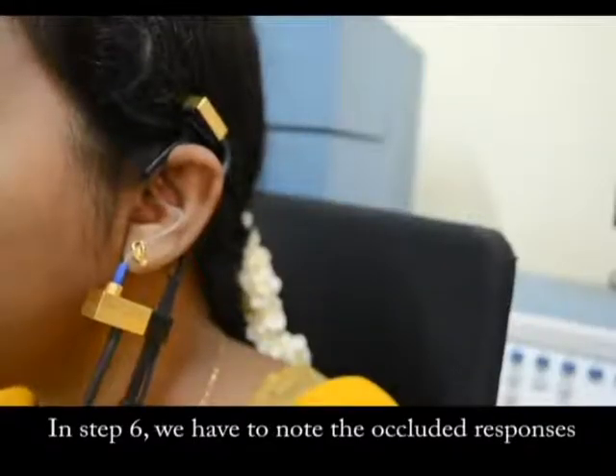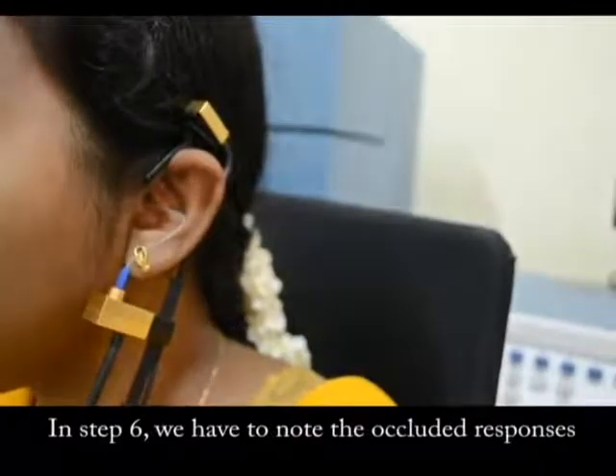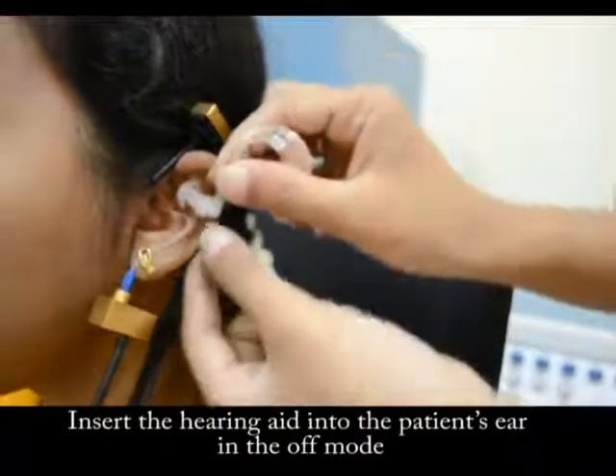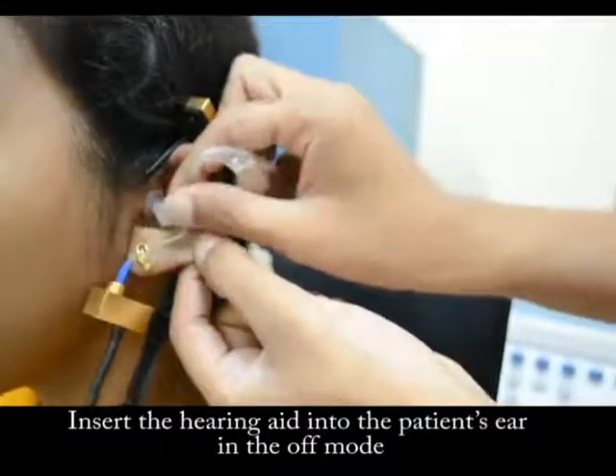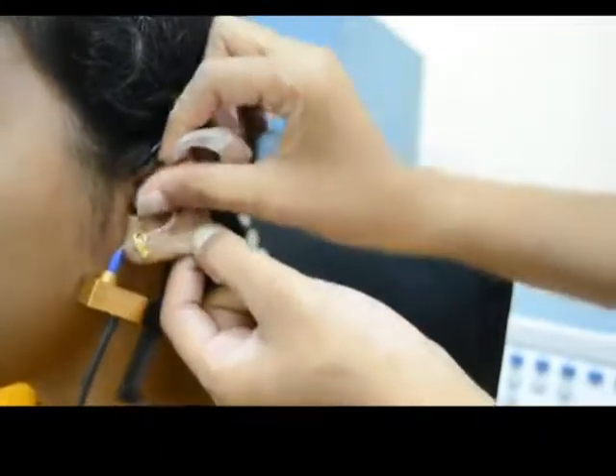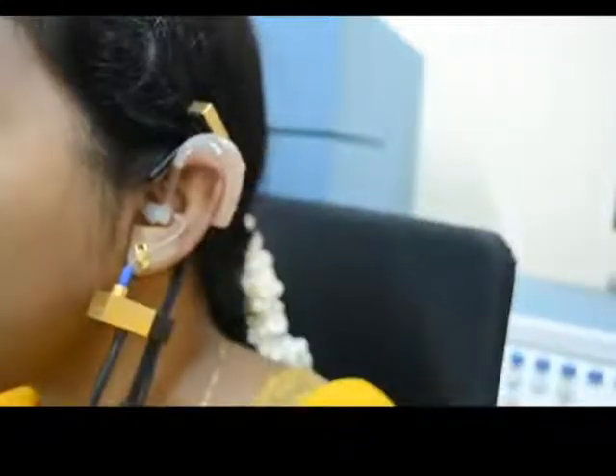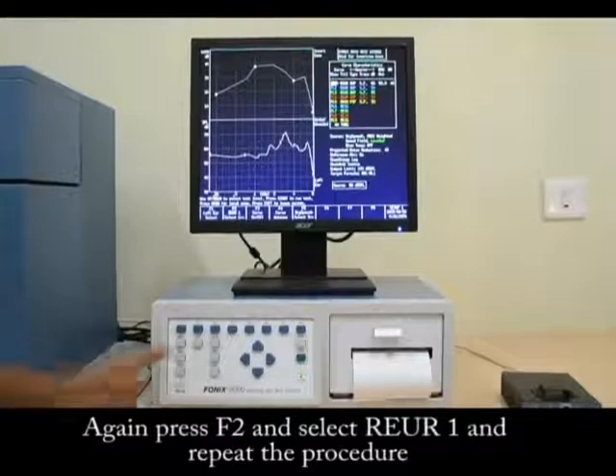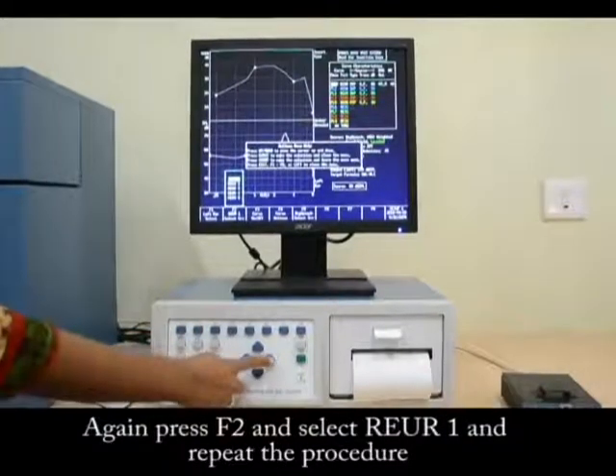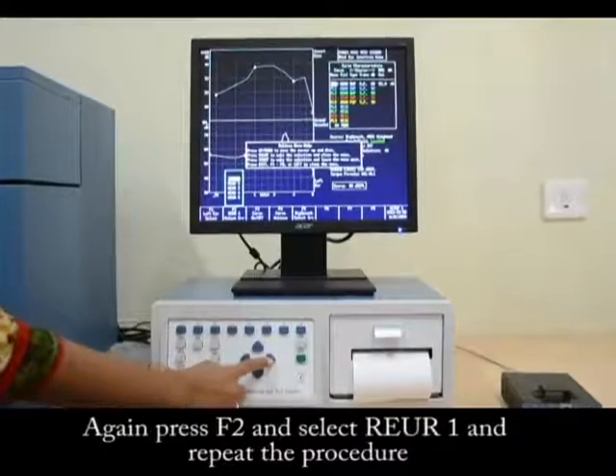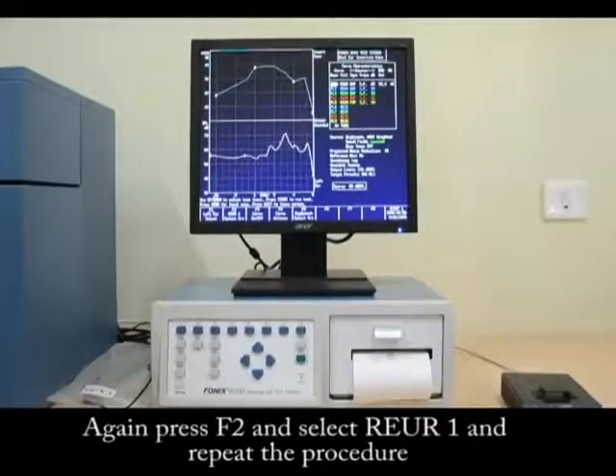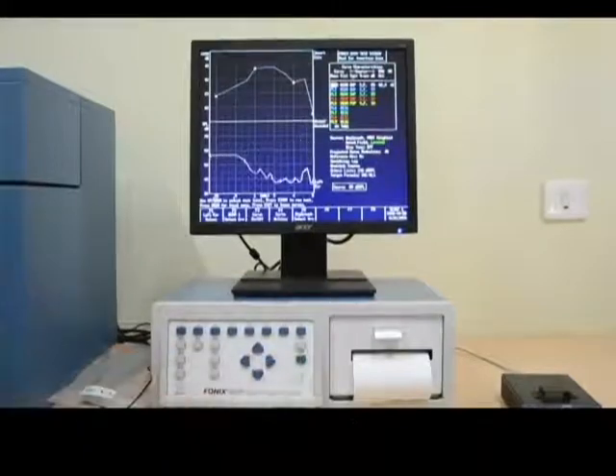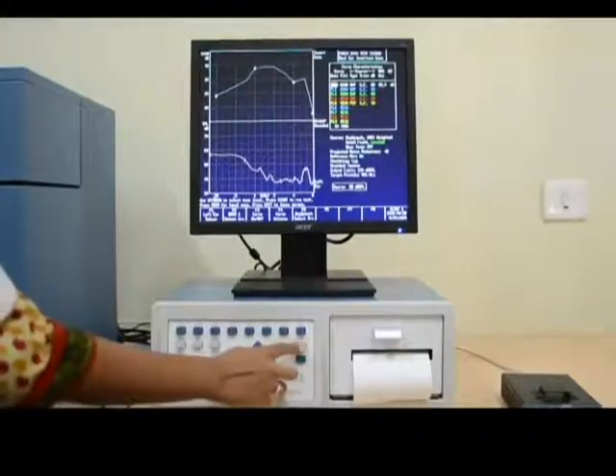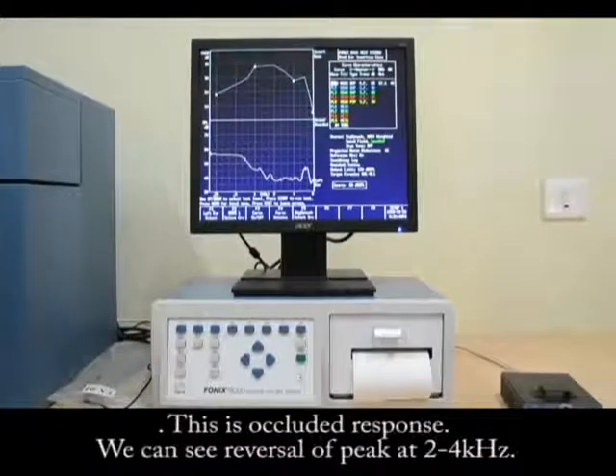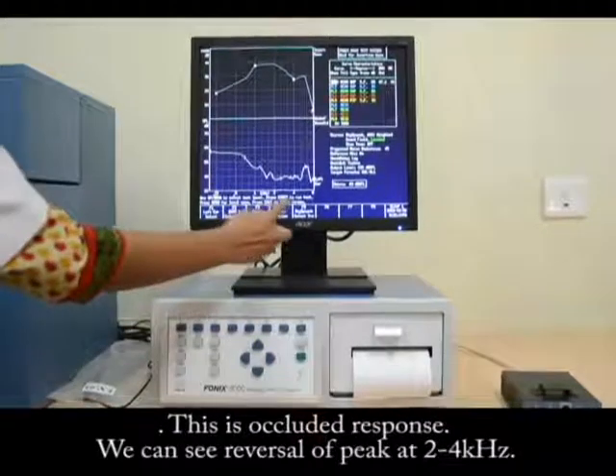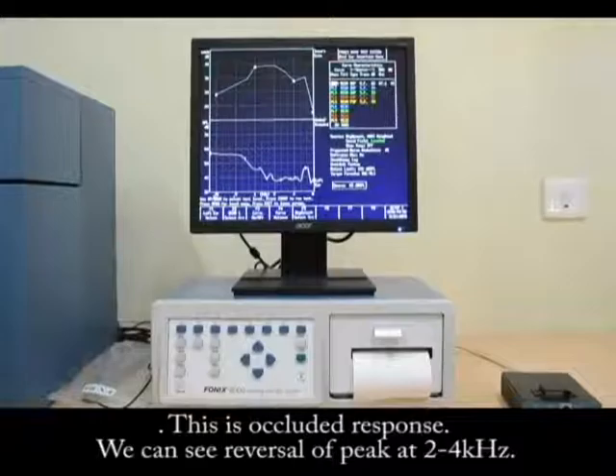In step 6, we have to note the occluded responses. Insert the hearing aid into the patient's ear in the off mode. Again, press F2 and select REUR1 and repeat the procedure. This is the occluded response. We can see reversal of the peak at 2 to 4 kHz.